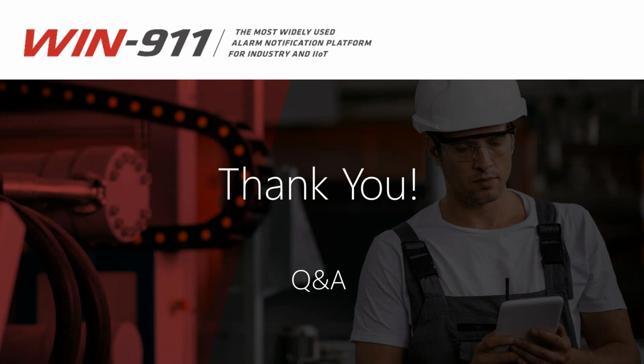Question was, did you say WIN-911 had to be installed on the FactoryTalk server, or could it be a FactoryTalk client machine? I was specifically talking about local applications. If it's a local application, then it's got to be installed on that local server. If it's a network application, it can be installed on a client machine, or it can be installed on a machine with no client actually running, but the client software has to be installed. So if it's local, WIN-911's got to be running on that local server. If it's network, then WIN-911 can technically be running on any machine as long as it is part of the directory.